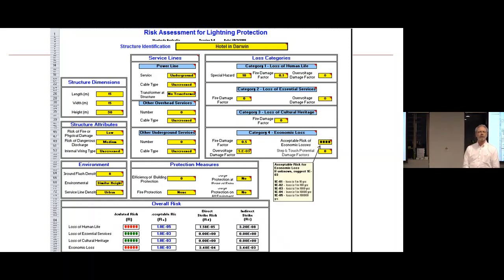The risk assessment, you also enter in down on the left there, bottom left, the environmental, whether other buildings are similar height or shorter or taller. Service line density, whether you're the only place on the end of the line or if there are a lot of others, because surges that are coming down the power lines, if you're the only destination for them, are going to cause you a lot more damage than if there are a lot of other connections.